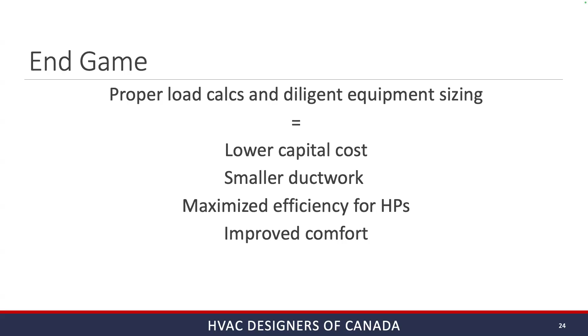Heat pumps are sensitive to sizing, right? If they short cycle - this is becoming less of an issue with inverters and variable capacity units, but it's still a truism - you lose maximum efficiency. Improved comfort is also a factor, again less important with variable capacity machines but not untrue, and the greatest greenhouse gas reductions come from proper sizing. This reminds us of the impact on the electrical grid, which is very important to some utilities - another spin-off thing we hadn't anticipated when we started the project.